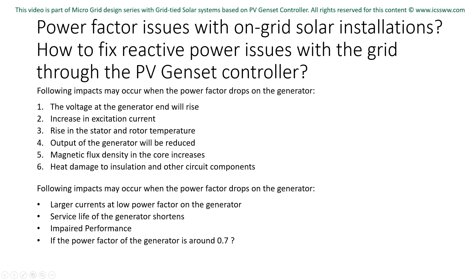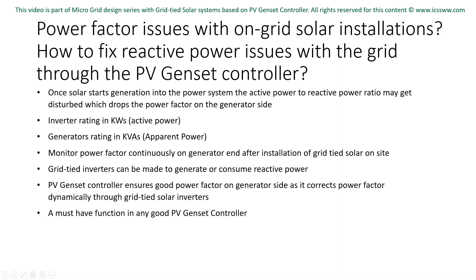For example, when the power factor of the generator is around 0.7, the output of the generator will be reduced by 8%. Interesting fact — most of the time when you buy an inverter, you will see its power rating in kilowatts, which is active power. On the other hand, when studying diesel or gas generators, evaluation of KVA, which is apparent power, is considered.